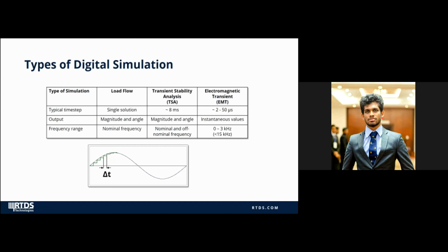Electromagnetic transient, or EMT, simulations are ideal for high-frequency applications. Detailed modeling of power systems can be made with EMT studies due to the small time step. EMT simulations operate under small time steps, around 2 to 50 microseconds. Typically, for power system applications, 50 microseconds is adequate. For power electronics, a small time step like 2 microseconds is reasonable.